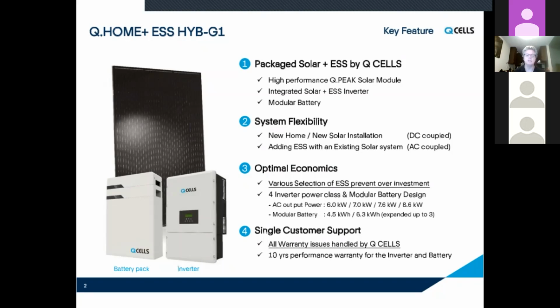The nice thing about all of our inverters is they will all work up to 7.5 kW in backup mode. This is pretty unique for the price point Renvu is offering. I do see other systems that can handle 50 or 60 amp loads, but with those systems you're talking about multiple inverters, batteries all over the wall, and very high price points as a result.